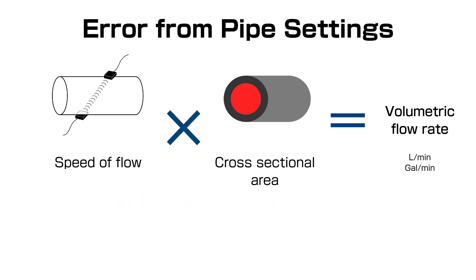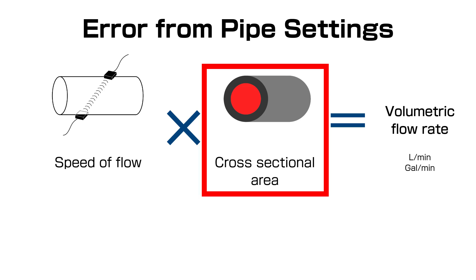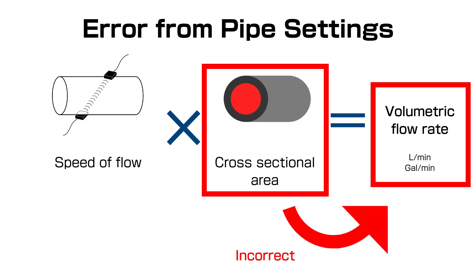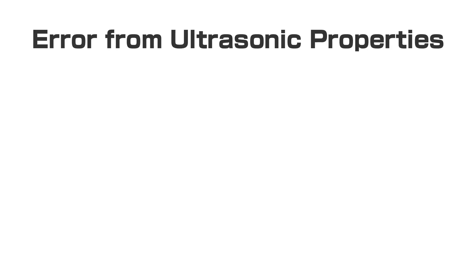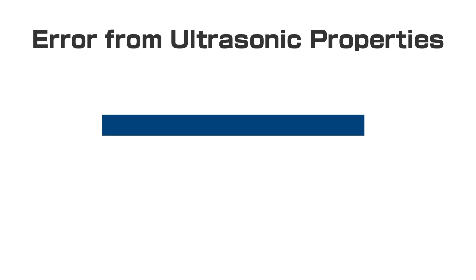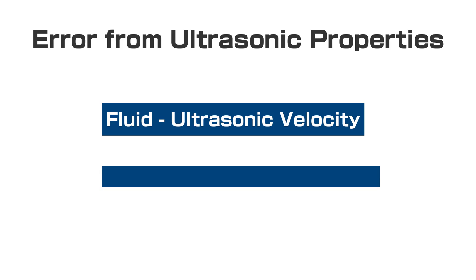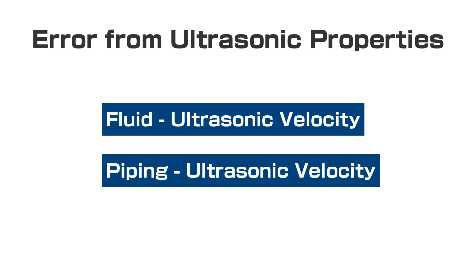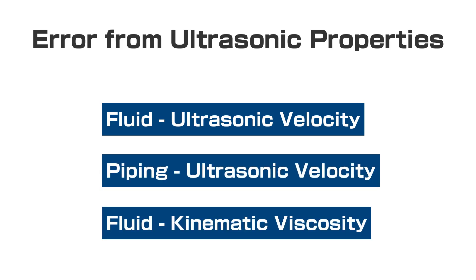If the sensor does not know the correct internal cross-sectional area of the pipe, the flow rate reading will be inaccurate. The last thing we'll discuss is the ultrasonic properties of the pipe or fluid. The properties in question are the ultrasonic velocity of the fluid, the ultrasonic velocity of the pipe material, or the kinematic viscosity of the liquid. It's important that the sensor knows the properties of the fluid or piping it's being used on to ensure optimal accuracy.